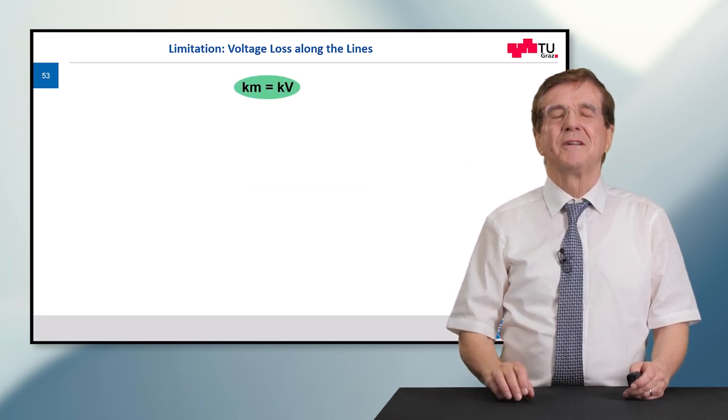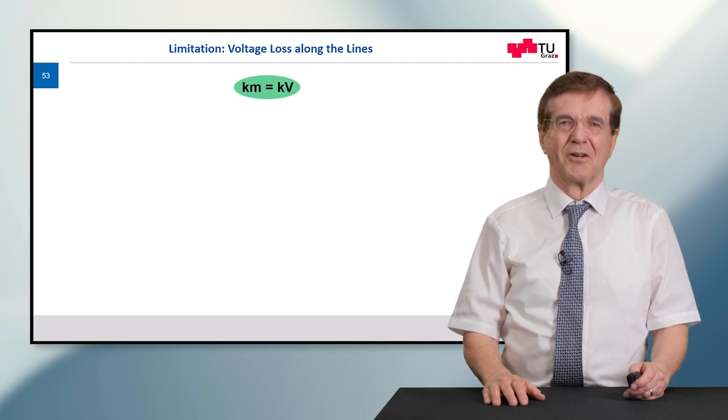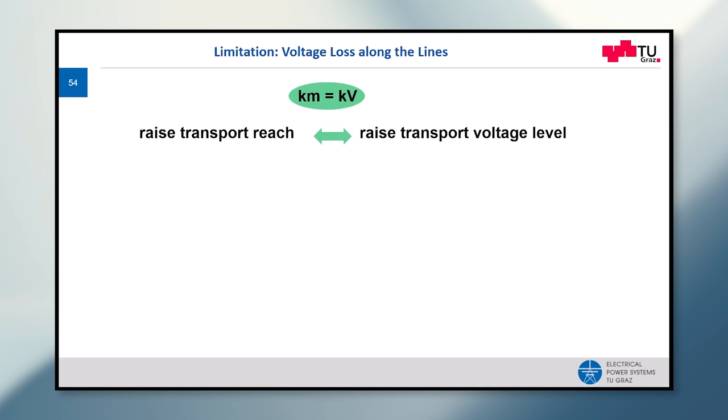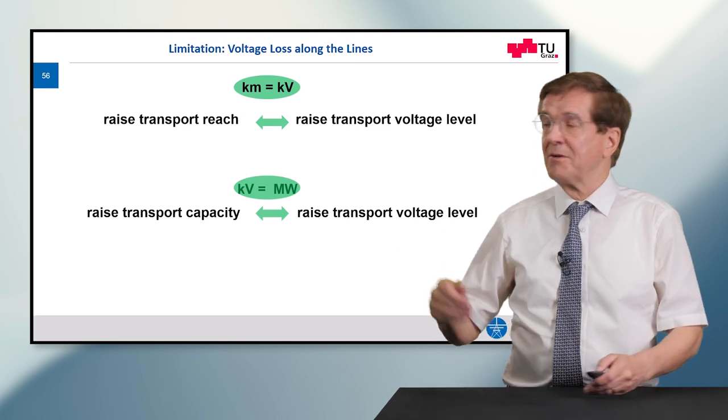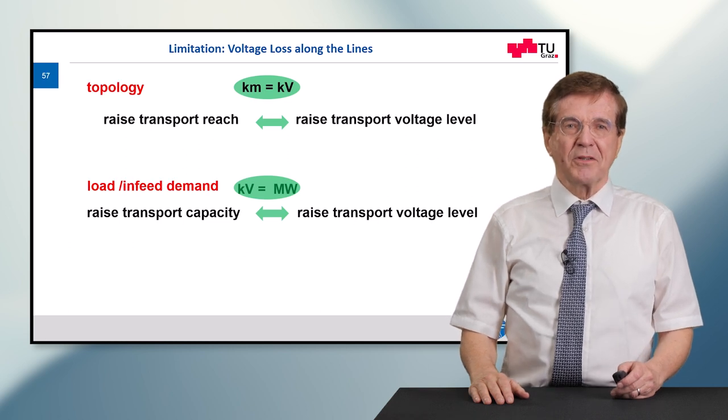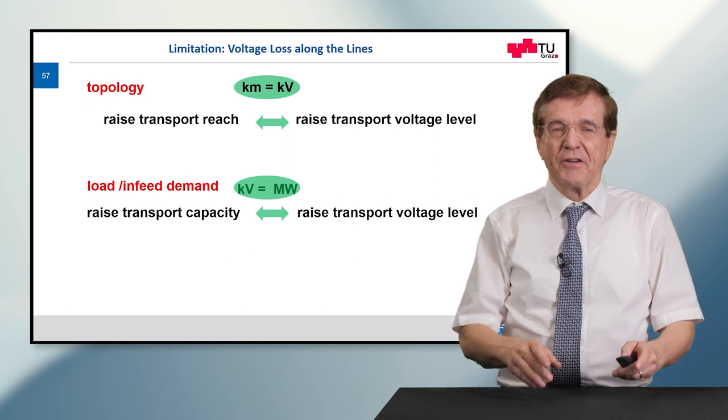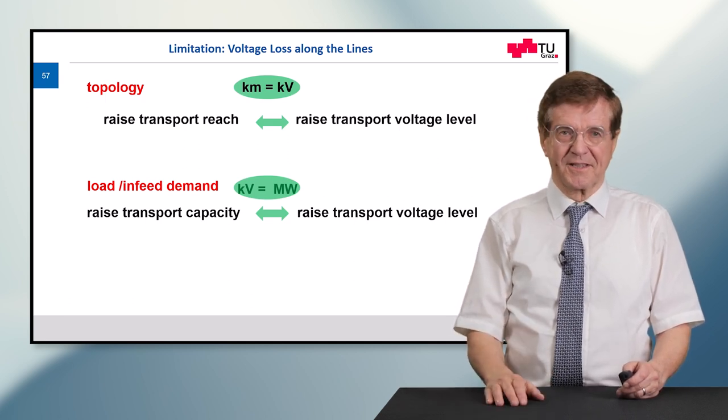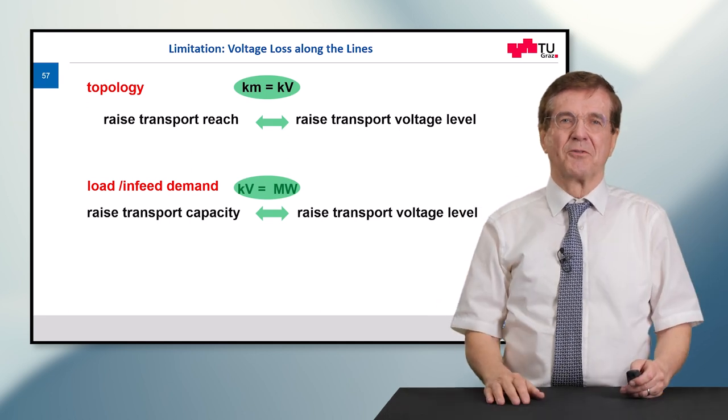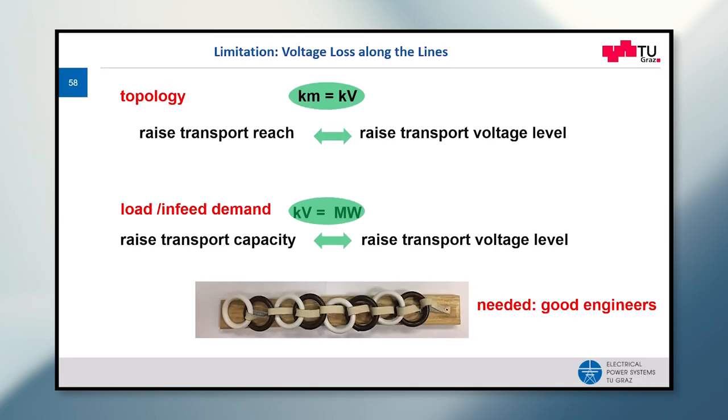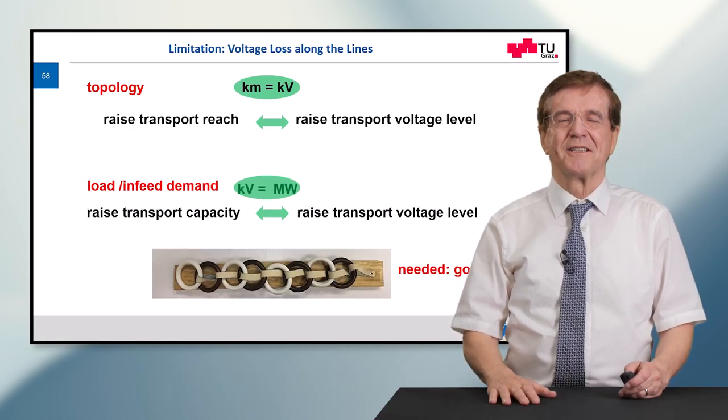Now we repeat these two crude but practical rules. So kilometers is more or less corresponding to the kilovolts, and this means to raise the transport reach we must raise the transport voltage level. The second line was already shown in the first part of my presentation. This is that the kilovolts corresponds to the megawatt that can be transported due to the current limitation. And here to raise the transport capacity we again must raise the transport voltage level. So the topology determines the distance over which this electric power has to be transported and the load and infeed demand determines the megawatts that are taken out of such a system. And to make these demands in a practical way applicable we need good engineers to solve this.